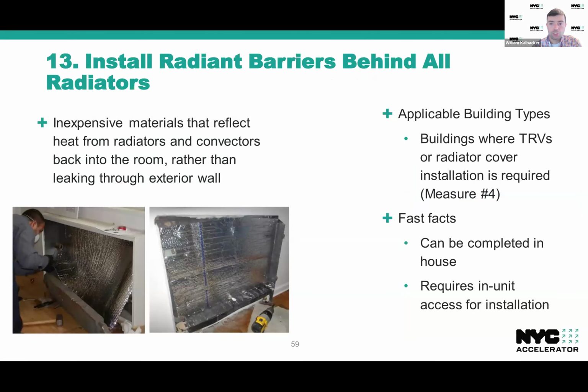The last item here, just touching back on radiant barriers: it is required that you install radiant barriers on appropriate radiators, convectors, cabinets, etc. Radiators radiate heat in all directions. They're typically placed up against a wall, and the space is on one side of the radiator. So if you have a radiator without a radiant barrier, it very well might be giving the wall a good amount of its heat. A barrier is basically a foil system that reflects heat back into the room to make sure that as much of the heat as possible from the radiator is actually heating the space that it's intended to, and not simply the wall next to the unit.